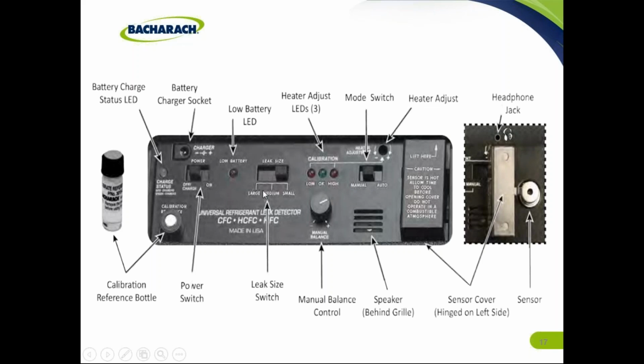Over here, you have your leak size switch. So you have a large leak, medium leak, and a small leak. The manual suggests you go in on large, and you look for large leaks and go through the system. If you don't find one, then depending on the refrigerant you have, you will go either medium or small. If you have a CFC or an HCFC refrigerant, you would put it on medium. If you have an HFC refrigerant, you put it on small. That's the way to protect the sensor.